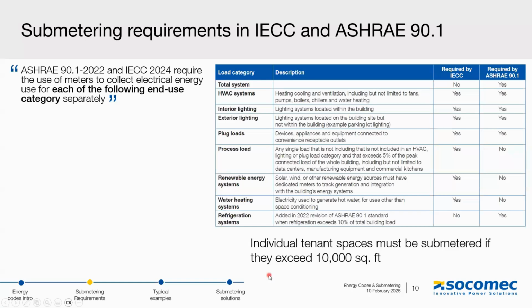They also require individual tenant spaces to be submetered if they exceed 10,000 square feet. So, if you have an office building with tenants that have more than 10,000 square feet of space, those tenants are supposed to be submetered individually.